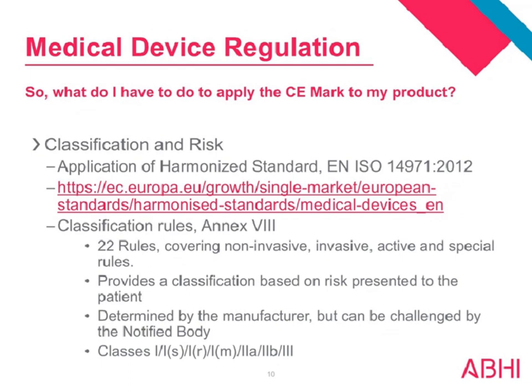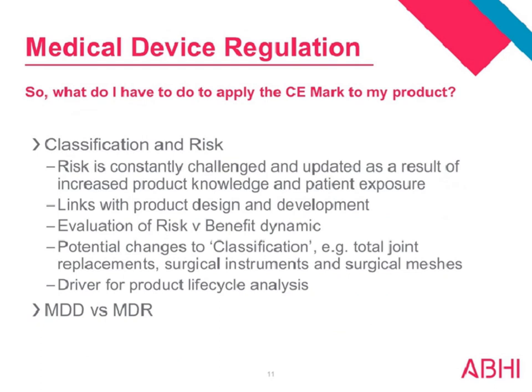The use of standards such as these are a route to demonstrating compliance. So when a notified body notices that you're using a specific standard for your product, the notified body is then happy that you're following the appropriate methods, and therefore the data that you're producing is appropriate for CE marking. The whole question of harmonisation is in debate at the moment, simply because the regulation is still needing a bunch of standards to be harmonised against the regulation itself. So if you are in that process of looking for standards, keep going back to that, because the number of harmonised standards will increase as time goes on.